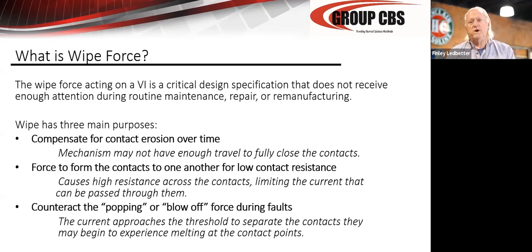When they reach their wear limit, they need to be replaced. If they're not, you can't maintain proper wipe. That means when you do have a fault, the breaker is not going to perform and protect the circuit correctly. So basically, maintain that force. Make sure those blow off or popping forces don't come into play. Check the wear on your vacuum interrupters at every maintenance cycle. When they approach that limit, replace them.